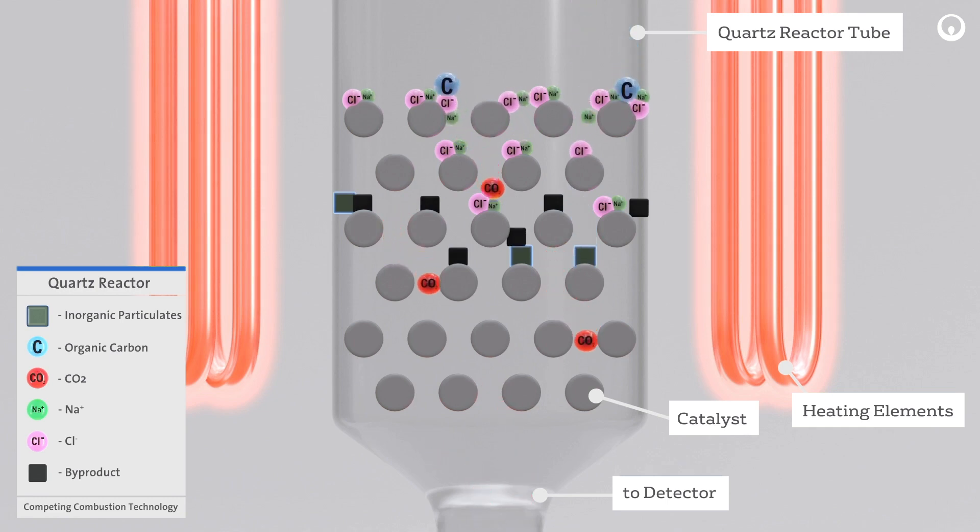The resulting carbon dioxide is carried out to the detector. All salts, particulates and resulting combustion byproducts remain inside the reactor tube and contaminate the platinum catalyst.